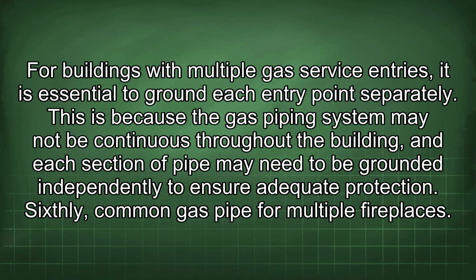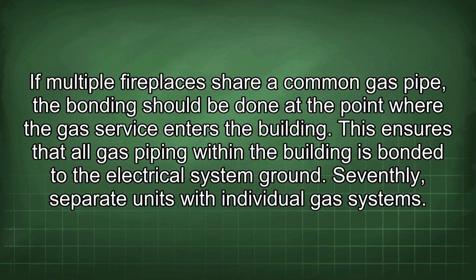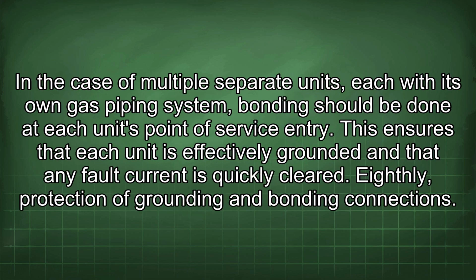Sixthly, common gas pipe for multiple fireplaces. If multiple fireplaces share a common gas pipe, the bonding should be done at the point where the gas service enters the building. This ensures that all gas piping within the building is bonded to the electrical system ground. Seventhly, separate units with individual gas systems. In the case of multiple separate units, each with its own gas piping system, bonding should be done at each unit's point of service entry. This ensures that each unit is effectively grounded and that any fault current is quickly cleared.